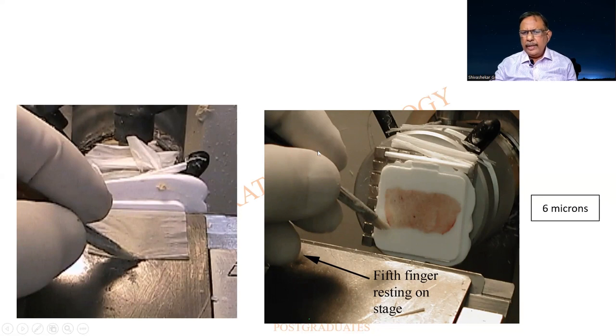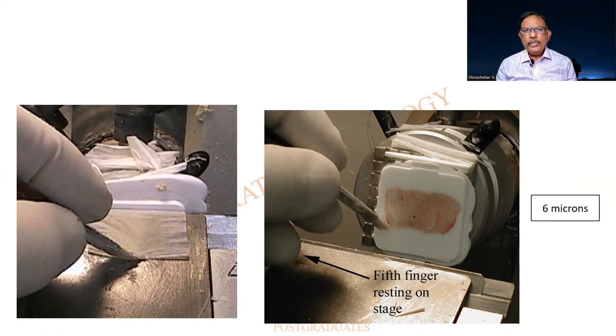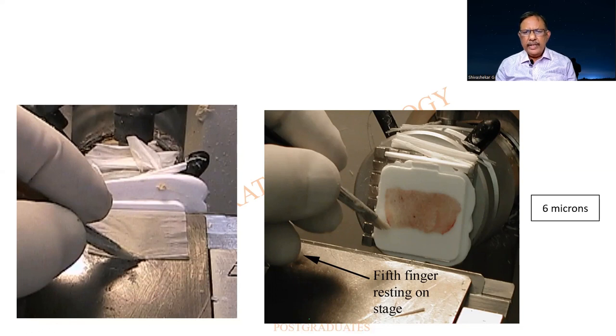What the technician is having in his hand is a brush. All the digits of his one hand — probably the left hand — are in action, while the right hand moves the microtome. There is a wrist plate here. It is a very delicate step. As one hand moves the microtome forward by five or six microns, simultaneously the other hand prevents the curling up of the section — which is an important complication in cryostat. It straightens it, the other hand cuts it, and straight sections are obtained. Such is the delicacy of a cryostat.